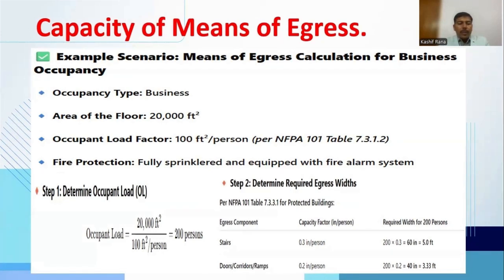First, we will calculate the occupant load factor, and then by multiplying with the egress factor, we can acquire the exit width. So the occupant load is equal to the covered area divided by the load factor. The covered area in this case is 20,000 square feet, and the occupant load factor is 100 for the business occupancy. So the occupant load is 200 persons.